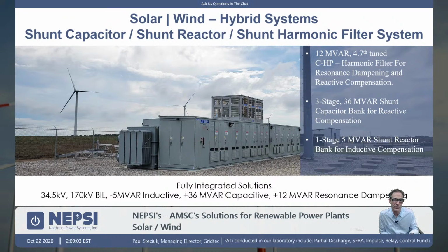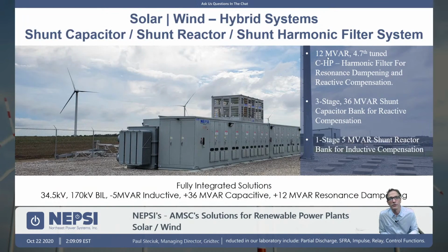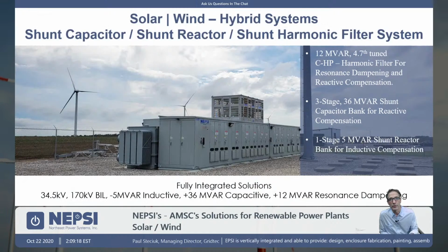So you can answer that problem up front by putting a C high pass filter in. I got it right there. This is also a 3-stage capacitor bank. So you get a 12 MVAR filter plus a 3-stage capacitor bank. Remember, the 12 MVAR filter provides reactive compensation, provides filtering, and it also prevents resonance. Those are the 3 reasons why you might want to install a filter on a system. The capacitor banks are there to supply reactive power also. So a total of 48 MVARs here.